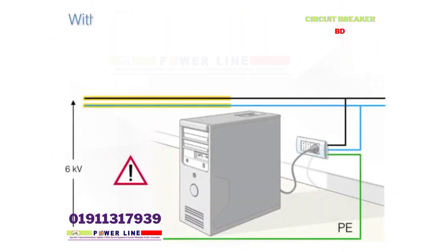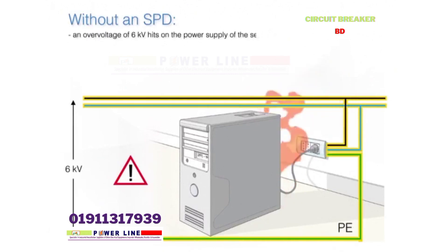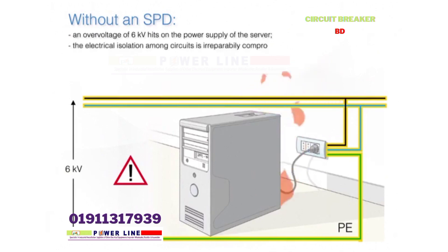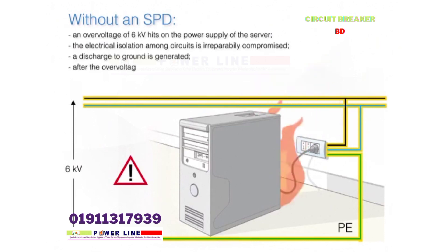Without an SPD, an overvoltage of 6 kilovolts hits the power supply of the server. The electrical isolation among circuits is irreparably compromised. A discharge to ground is generated.